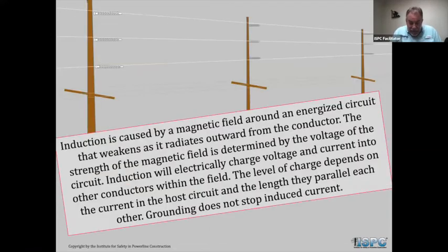So in the electric line, there's a return current on the system neutral. So what do we bond the system neutral to? The pole ground at just about every pole. So what do we bond the messenger wire to? The ground, which is bonded to the system neutral, which has current flowing on it. Now, how much current is flowing on it?